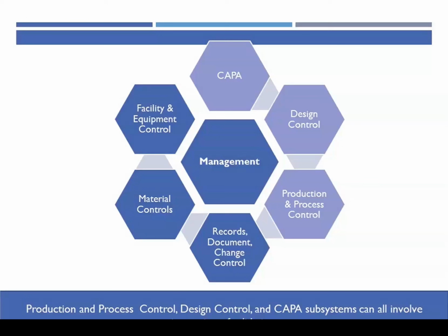The FDA always looks at CAPA, and when they look at CAPA, they're going to look for indicators of quality problems, of validation problems, and they're going to pull your validation reports and see what went wrong. If the FDA looks at design controls, they're going to want to see that design validation was done on product from a validated process, and that you transferred the design to manufacturing. They're going to pull the thread and see how you did process validation.